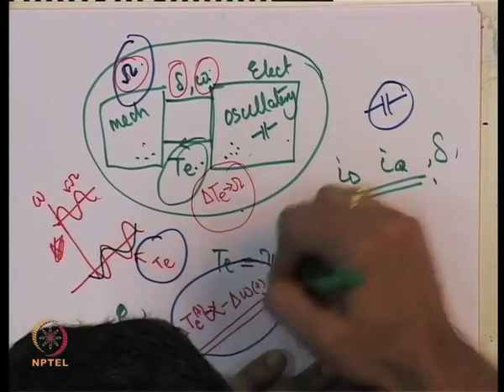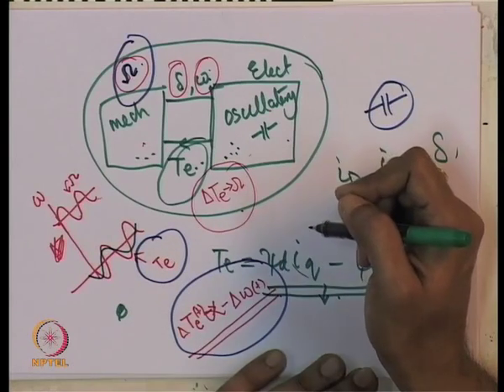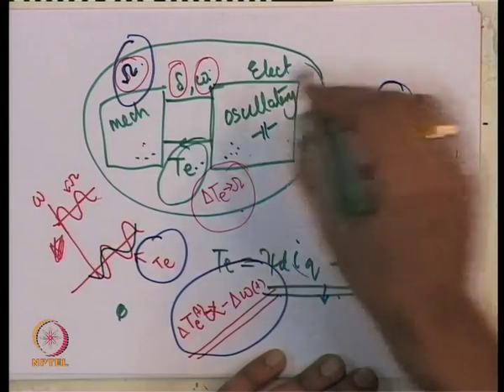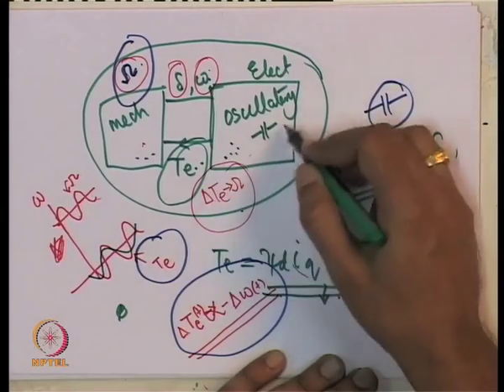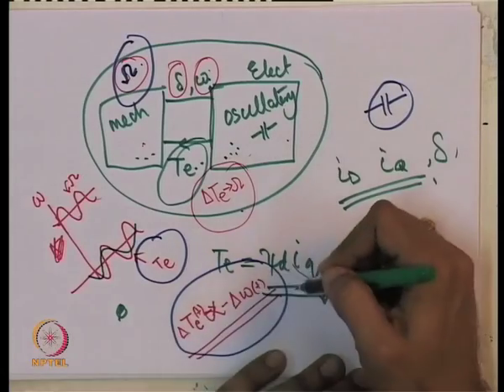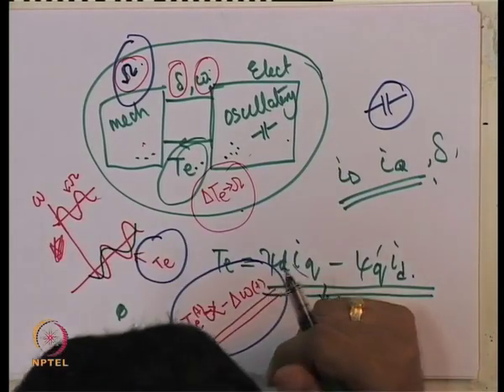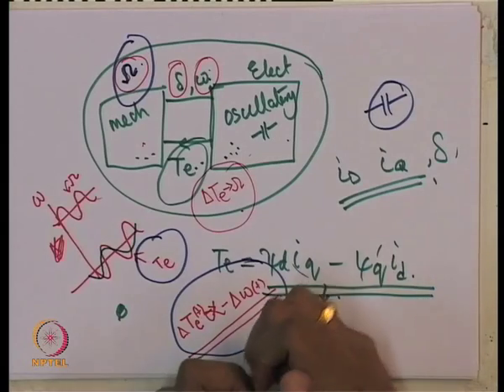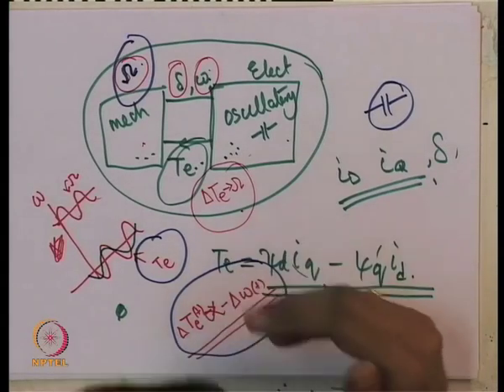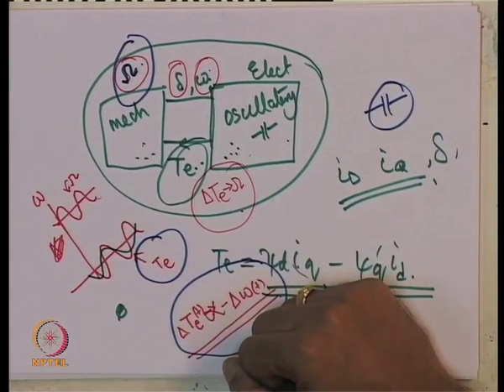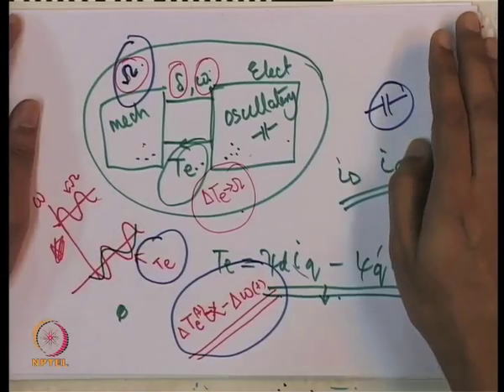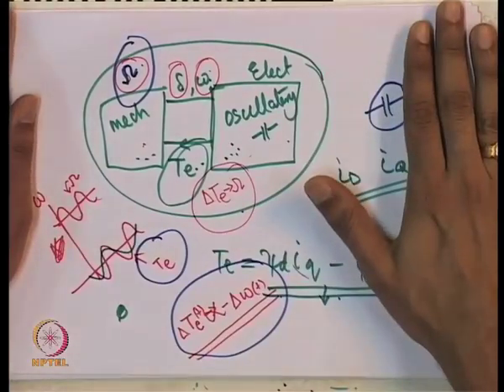This problem will be very much enhanced in case this torsional frequency equals the sub-synchronous oscillatory frequency of the network in the D-Q reference frame. When the torsional oscillation frequency equals the network's sub-synchronous natural frequency, the electrical torque variation can be very large and cause significant instability. The electrical torque may really cause a very adverse reaction and the oscillation may start growing — that is why this is called sub-synchronous resonance.